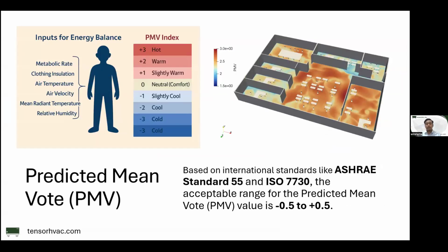So the first parameter defined by ASHRAE 55, which is actually not only used in ASHRAE but also in other standards like ISO 7730, is the predicted mean vote, which is basically a combination of metabolic rate, clothing insulation, air temperature, air velocity, like we discussed previously, and the mean radiant temperature. That's why I introduced you to the mean radiant temperature, and the relative humidity. All of these parameters are converted into a single parameter with quite long equations, so I will not display it here. And that basically tells us how the occupants feel in that room.